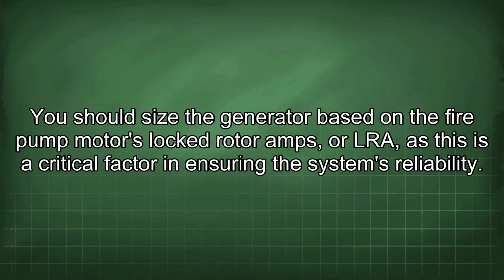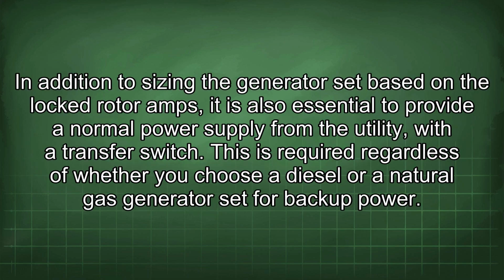You should size the generator based on the fire pump motor's locked rotor amps, or LRA, as this is a critical factor in ensuring the system's reliability. In addition to sizing the generator set based on the locked rotor amps, it is also essential to provide a normal power supply from the utility with a transfer switch. This is required regardless of whether you choose a diesel or a natural gas generator set for backup power.